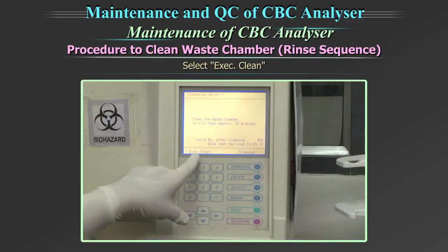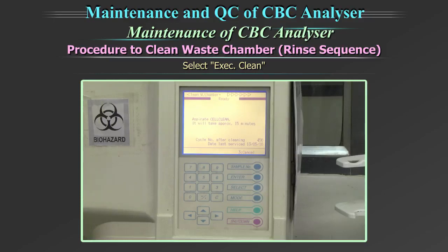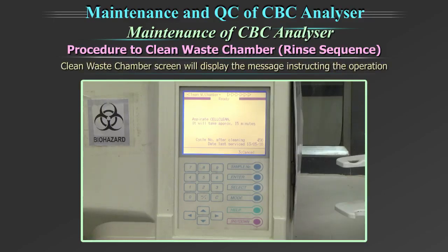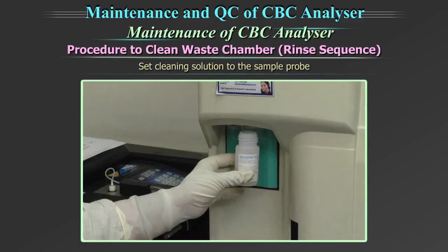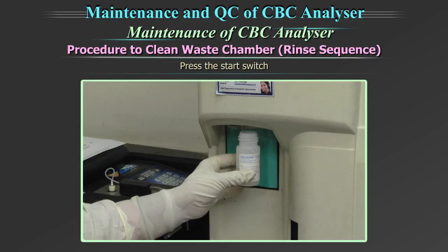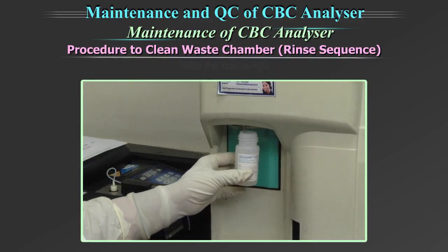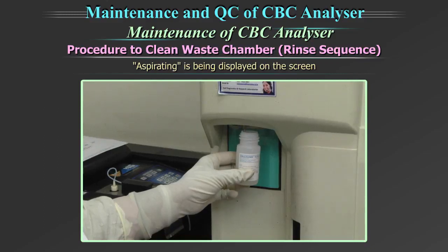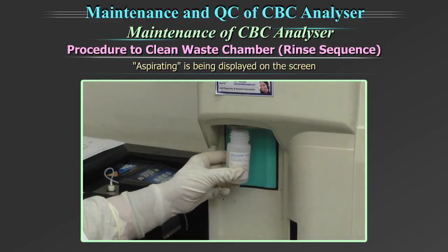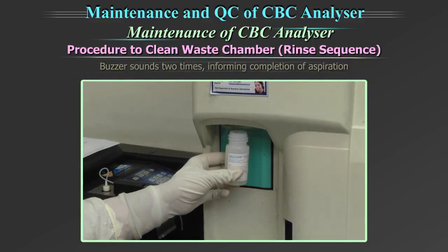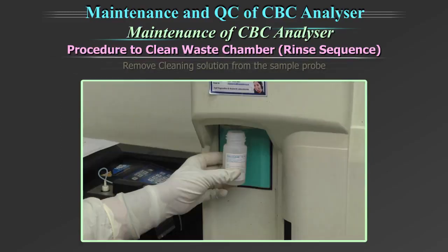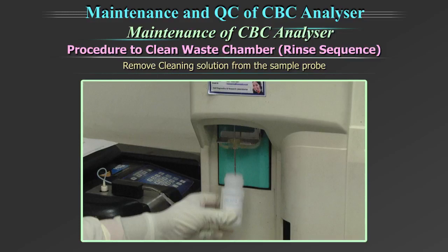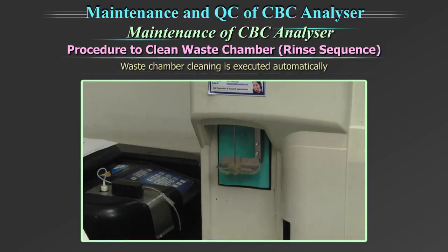Select Execute Clean on the scheduled maintenance message screen. The Clean Waste Chamber screen will display the message instructing the operation. Set the cleaning solution to the sample probe and press the Start switch in this status. While aspirating is being displayed on the screen, keep holding the cleaning solution in the same position. When the buzzer sounds 2 times, informing completion of aspiration, remove the cleaning solution from the probe. After that, the waste chamber cleaning is executed automatically.